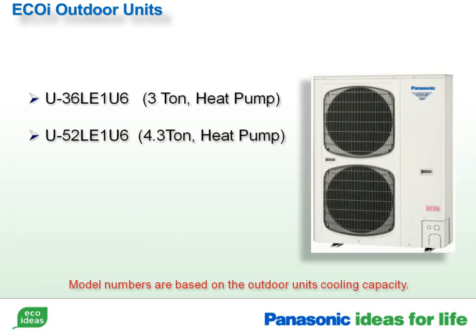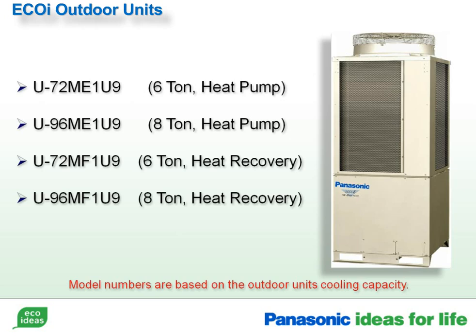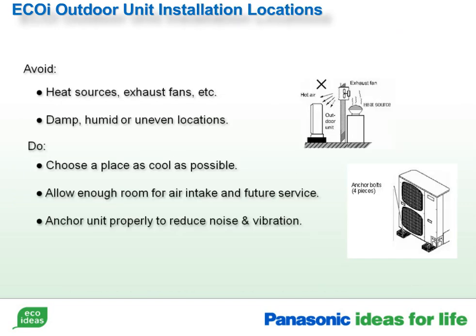The U-36-LE is a 3-ton unit, and the U-52-LE is a 4.3-ton heat pump. The U-ME heat pump and the U-MF heat recovery units are available in 6 and 8-ton. Model numbers are based on the condenser cooling capacity. When deciding on a location for the condenser or condensers, you should choose a place that is as cool as possible, and be sure to avoid any heat sources, damp, humid, or uneven locations. Allow enough room for airflow and future service.